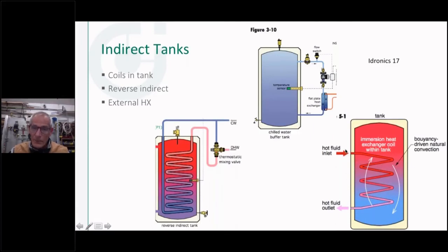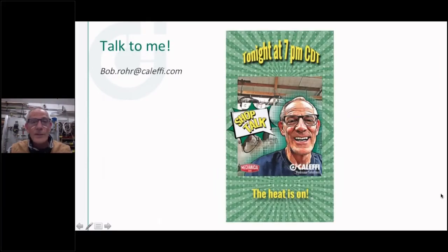Now, I've seen these piped both ways. Some people say, well, wouldn't you want to put the hot water in at the bottom where the coldest water is? Yeah, you could do that, but the intention here is I want to heat the top part of this tank as quickly as possible. So if I've got a call for domestic hot water, I'm heating the top of the tank first. It's like an electric water heater. You know how the top element always kicks on first, raises the temperature at the top of the tank, so you've got hot water, and then it kicks down to the bottom element to finish it off. So either way.